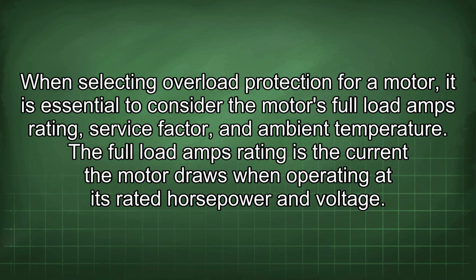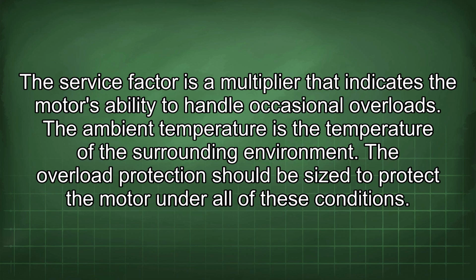When selecting overload protection for a motor, it is essential to consider the motor's full load amps rating, service factor, and ambient temperature. The full load amps rating is the current the motor draws when operating at its rated horsepower and voltage. The service factor is a multiplier that indicates the motor's ability to handle occasional overloads. The ambient temperature is the temperature of the surrounding environment. The overload protection should be sized to protect the motor under all of these conditions.